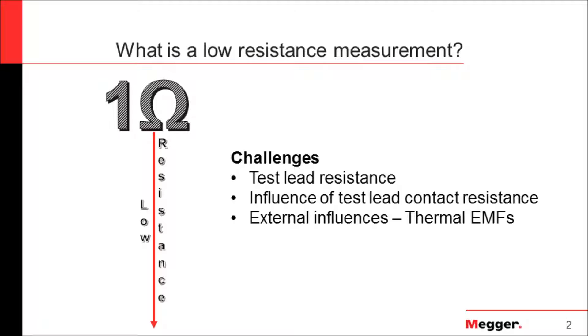Whenever we are measuring resistance values below 1 ohm, we consider those as low resistance, and we should be aware that at those very low levels, we're going to face a few challenges — like the influence of the test lead resistance, poor test lead contact, and if we have a joint between different metals, then we will have thermal EMF developed in the junction.